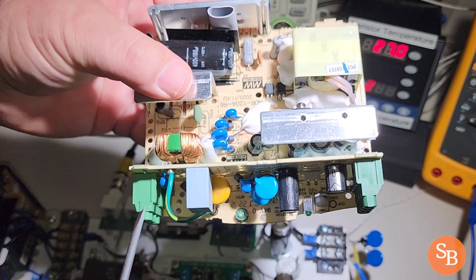So what happens is if the input goes over voltage for longer than maybe half a second to a second, the fuse blows and protects the rest of the circuit from catching fire. But once the fuse has gone, it's not a user-replaceable fuse, so the whole assembly has to be replaced.